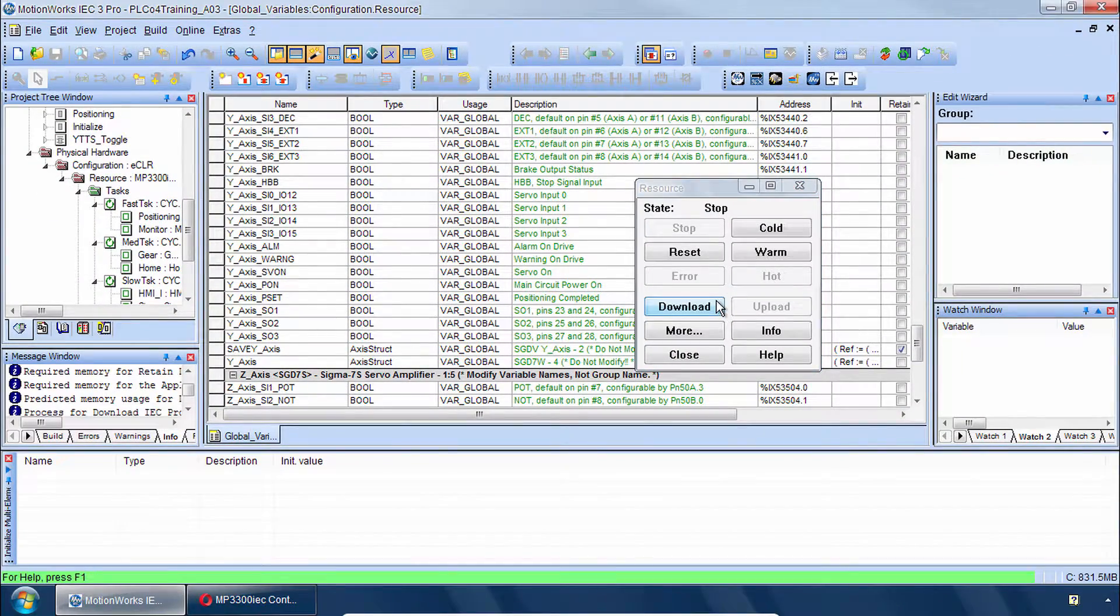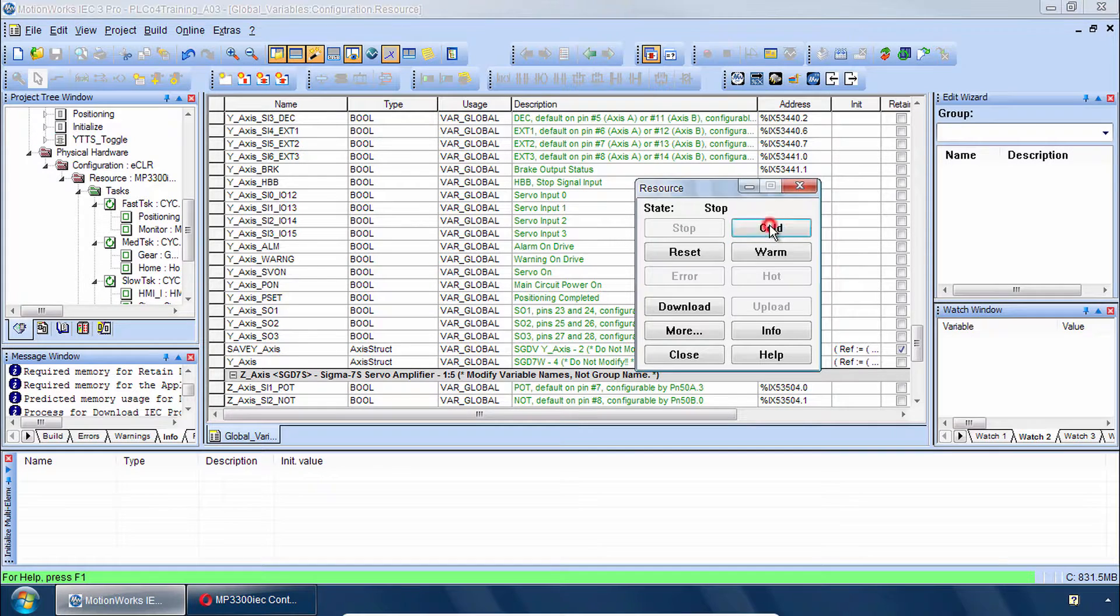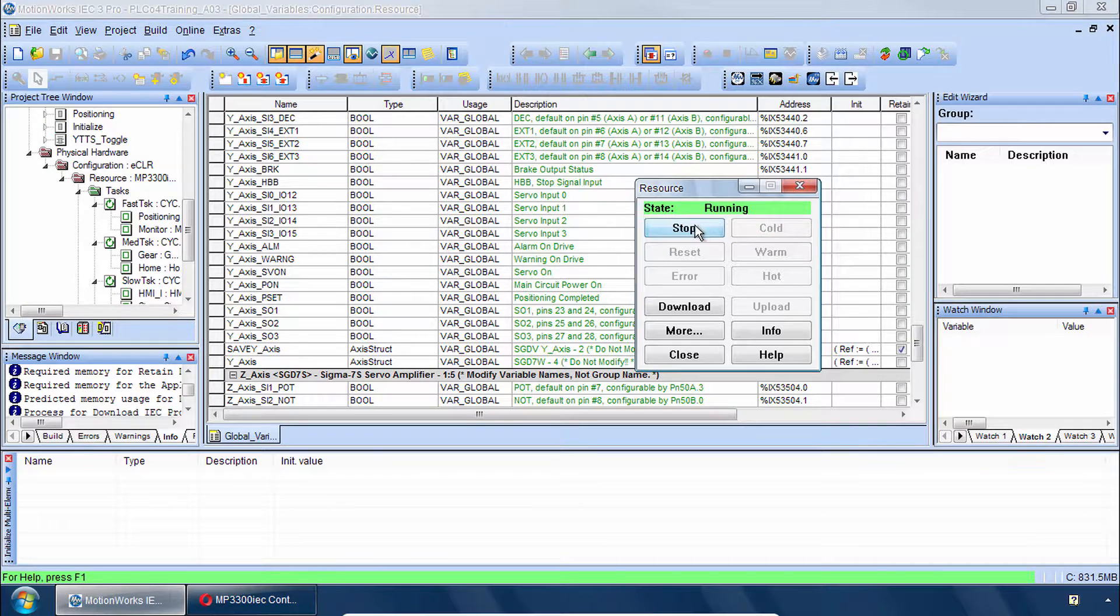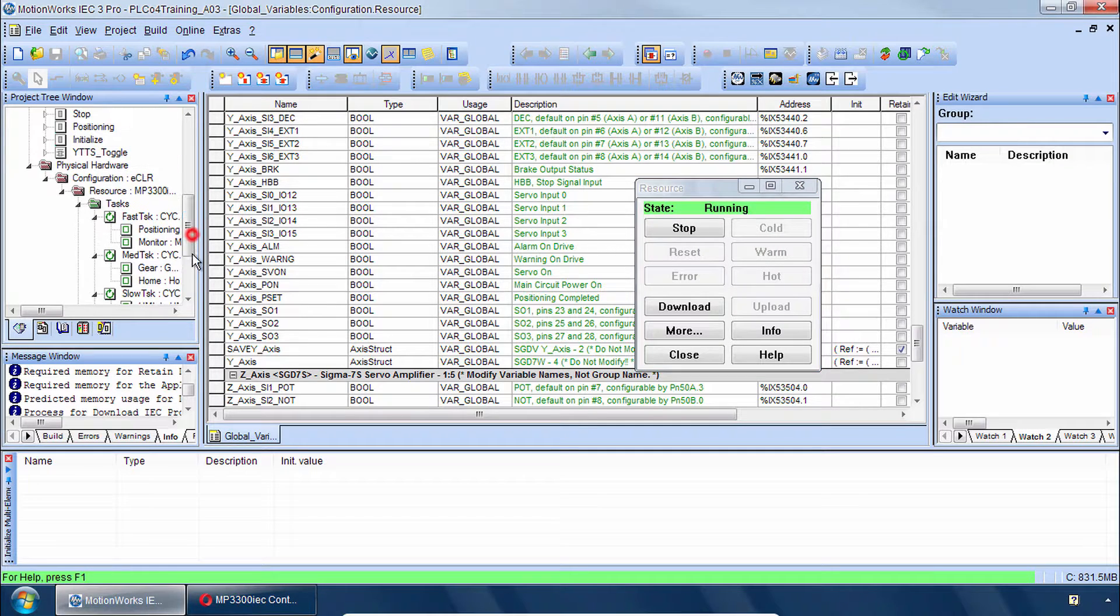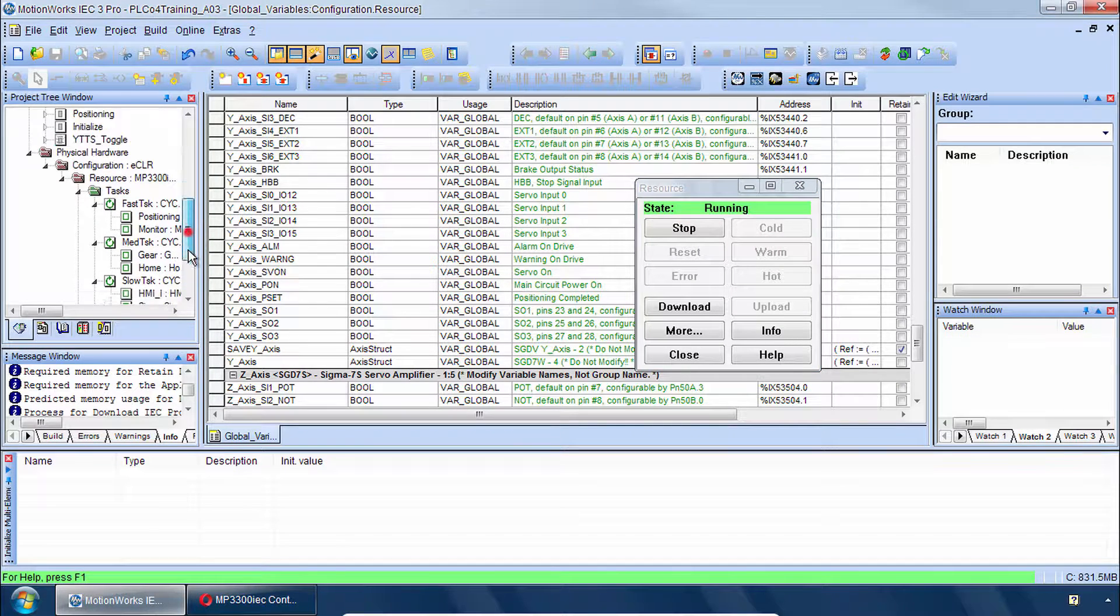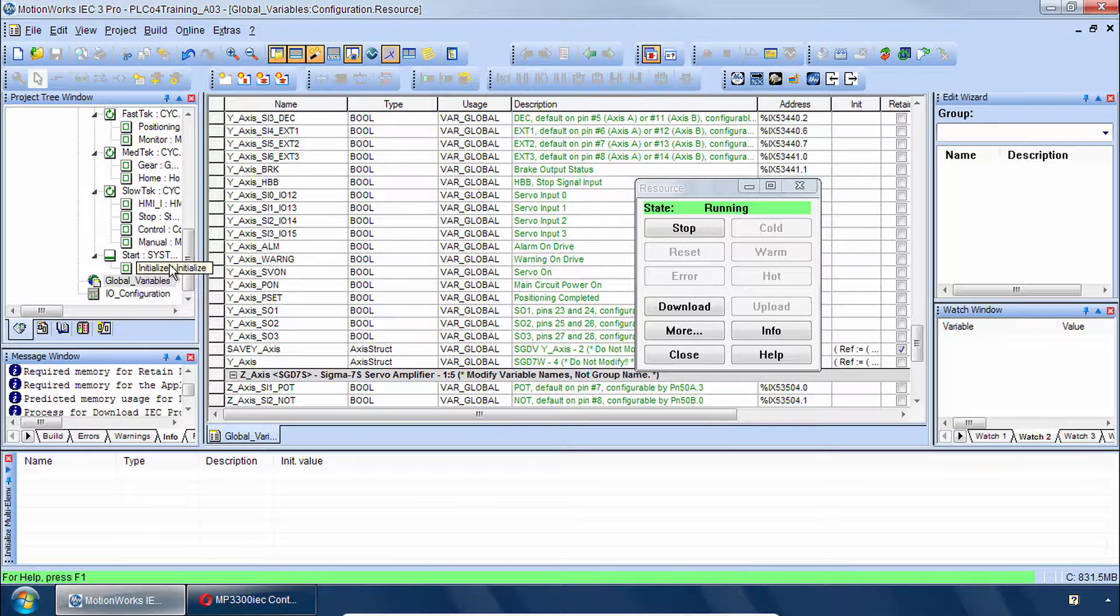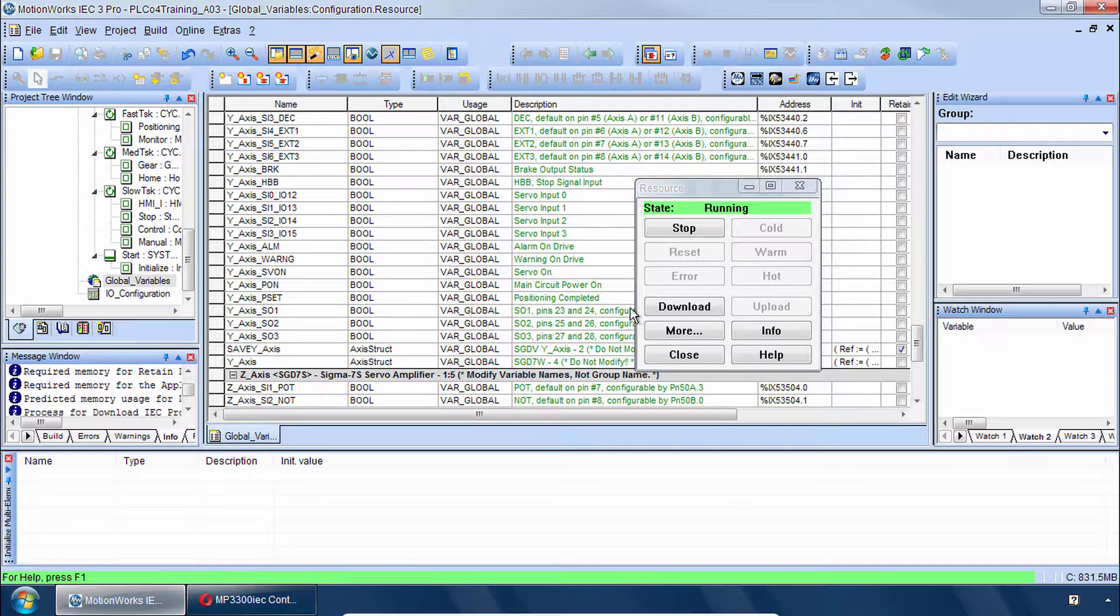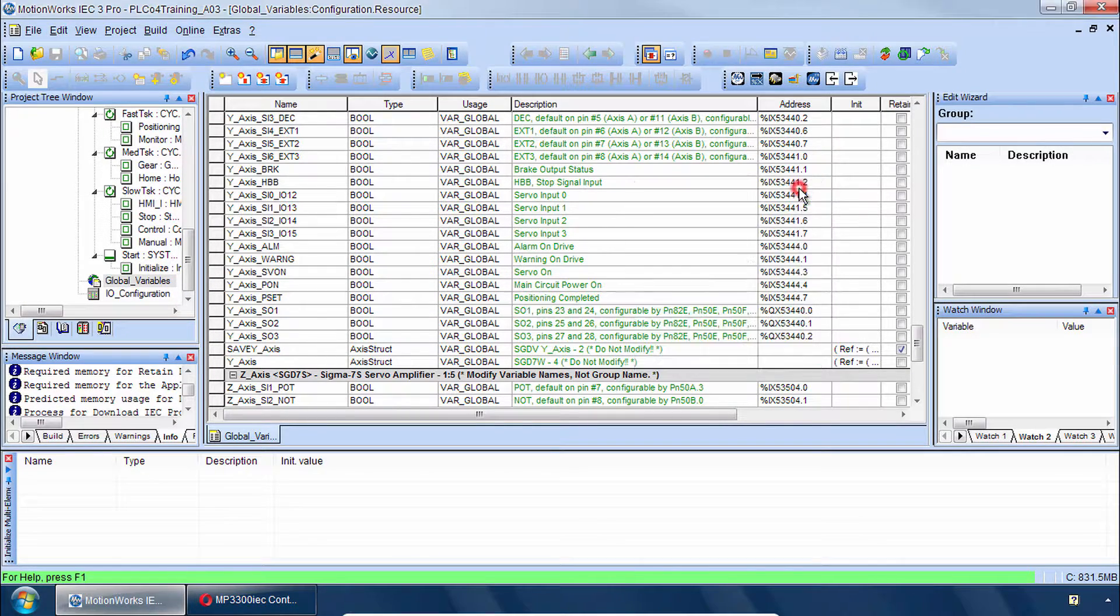And you may see a message that Warm Start is not possible. So for this first time we'll do a Cold Start, Stop and then a Warm Start. Because we do have to be sure that all the variables initialize. And that the Start Initialize program does run. OK we can close this resource.